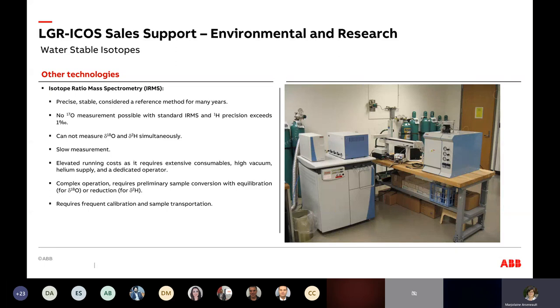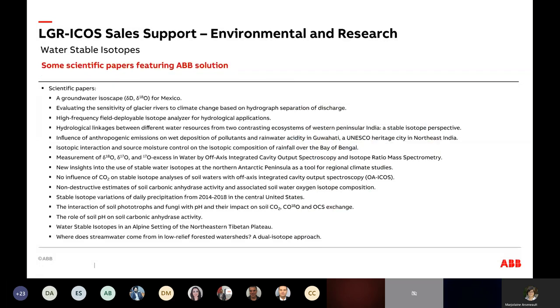There are no consumables for ICOS, unlike mass spectrometry, and there's no need for a dedicated trained operator. For the liquid analyzer, for example, it can be configured and run by itself for hours. We have scientific papers featuring ABB solutions — they will be available if you want them, just ask. This is not a limited list of published work. We are quite proud of our product and it's been widely used.